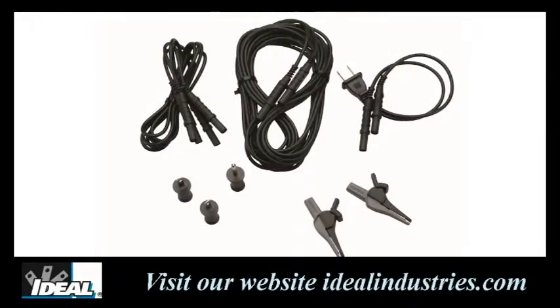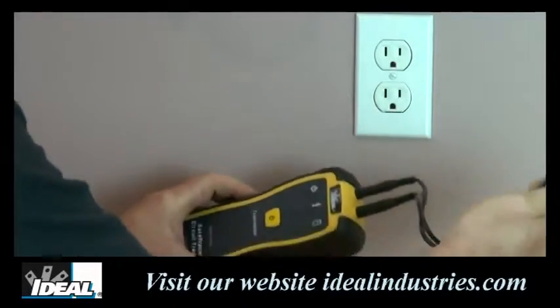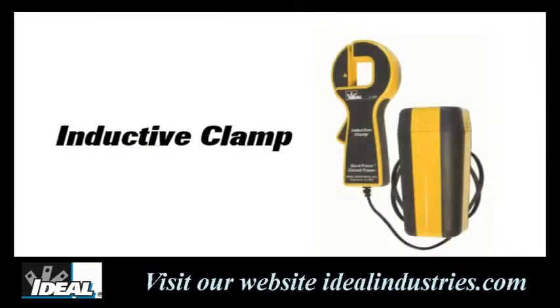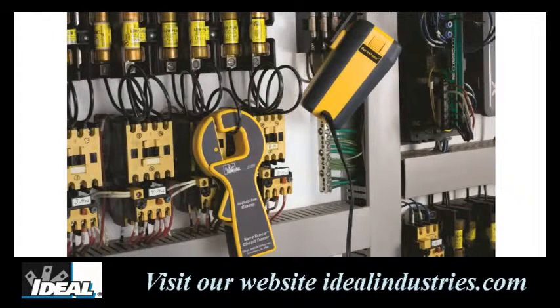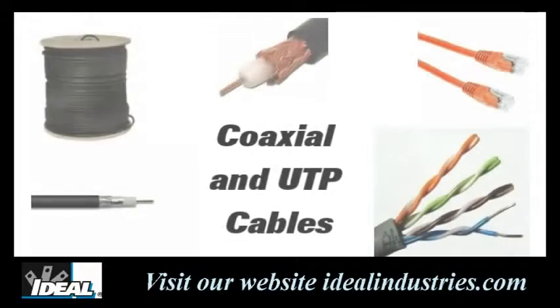The circuit tracer can be used to trace a variety of cables and comes with a variety of adapter cables to either plug the transmitter directly into electrical outlets or use alligator clips to clamp it to the end of a conductor. You can even get an inductive clamp that clamps around a cable and induces a signal into it when no exposed ends of the cable are available. While primarily used for tracing electrical cables, you'll find it also works on coaxial and UTP cabling.